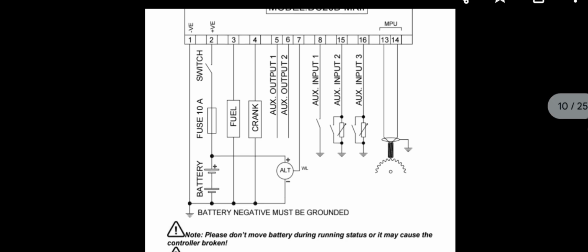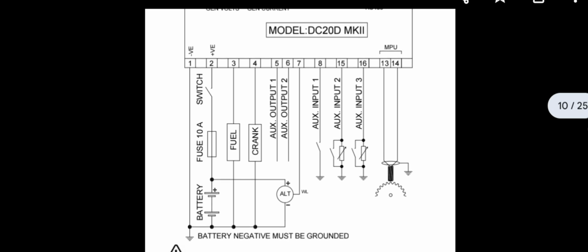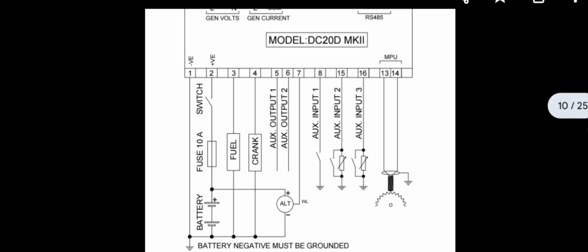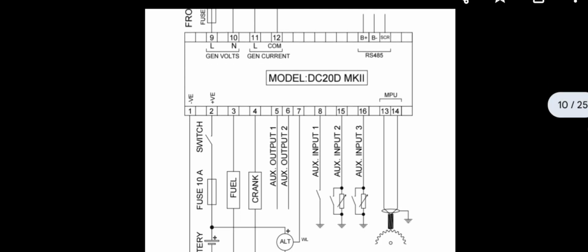Okay, and after that the pin number 4 for the crank starter motor relay coil only, and after that pins 5, 6, this auxiliary output you can use it for anything. Okay, and pin number 7 is going to the charging alternator warning light, and after that pin 8, 15 and 16, this is the auxiliary input. Okay, you can use for like oil pressure sensor, temperature sensors, coolant temperature sensors. Okay, low fuel levels. Okay, after that, as you can see, pin 13 and 14, this is for the MPU inputs. Okay, after that, upper side, as you can see, pin 9 and pin 10, that's the genset voltages and also the genset current transformer.